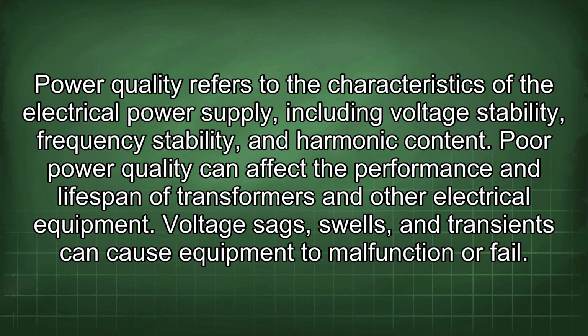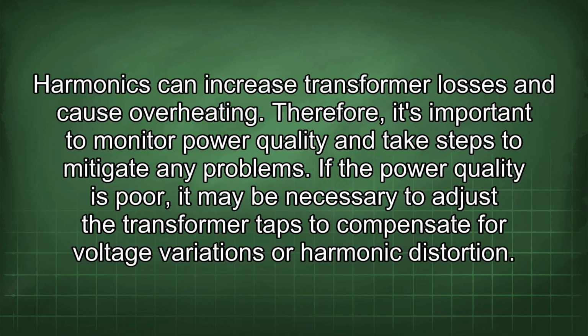Power quality refers to the characteristics of the electrical power supply, including voltage stability, frequency stability, and harmonic content. Poor power quality can affect the performance and lifespan of transformers and other electrical equipment. Voltage sags, swells, and transients can cause equipment to malfunction or fail. Harmonics can increase transformer losses and cause overheating. Therefore, it's important to monitor power quality and take steps to mitigate any problems.